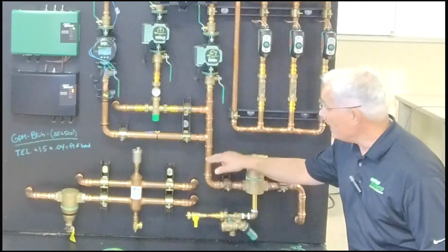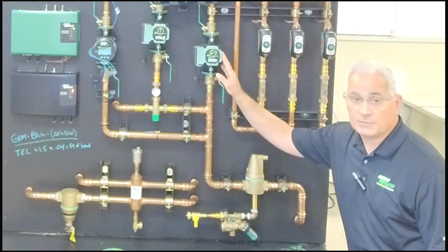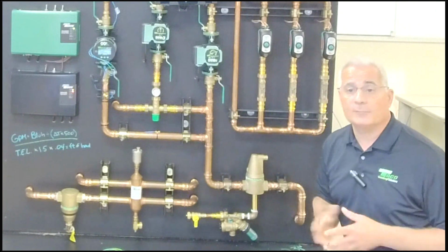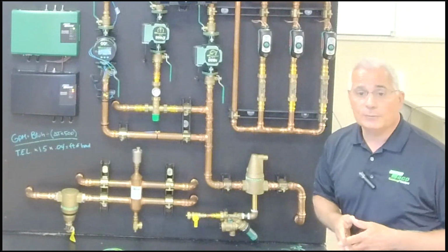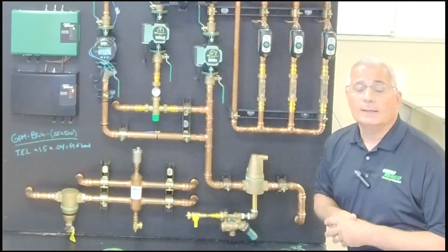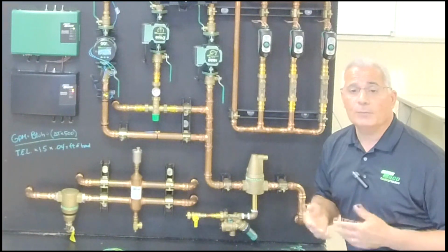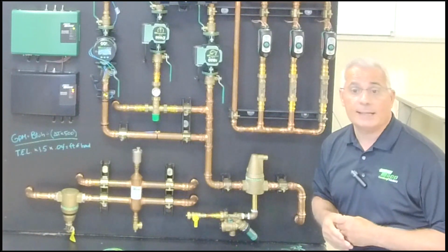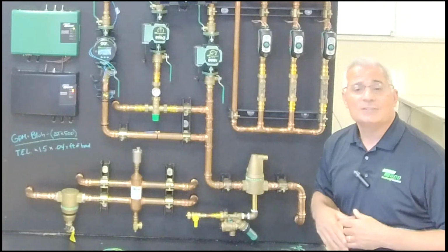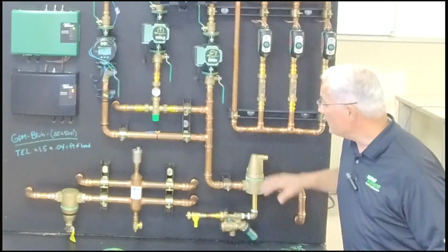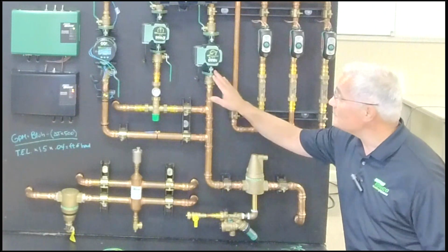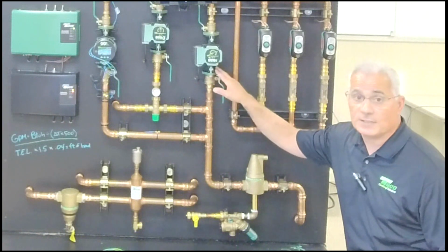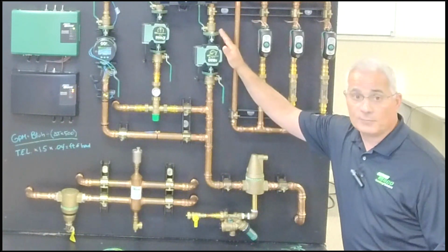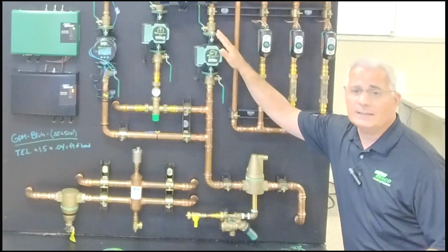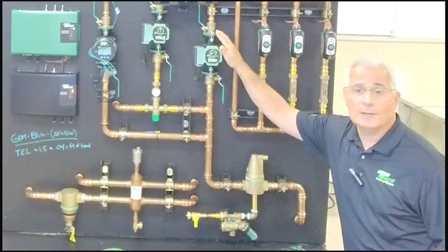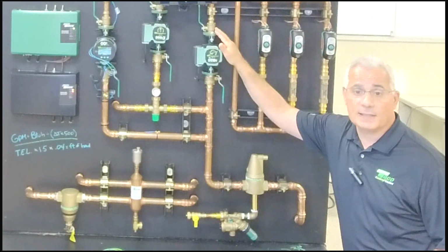As you follow the piping up, this would be our system circulator. So we are pumping away from our expansion tank. If you recall from previous TACO or Wales Darby webinars, pumping away means the circulator is going to be adding positive pressure to our system. It's going to work to your advantage. So if I had 12 PSI on this side, I'll see 12 PSI here because this is my suction side, but my positive pressure will be up here. Let's say for argument's sake, it's an additional 4. I'll have 16 PSI here.